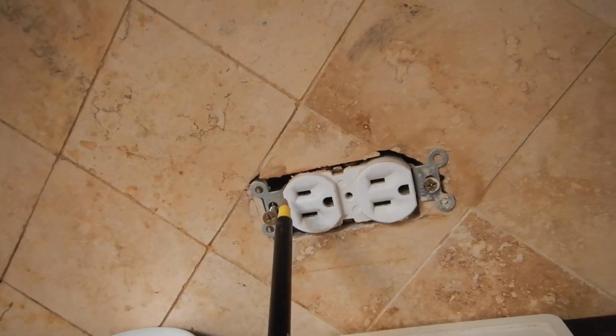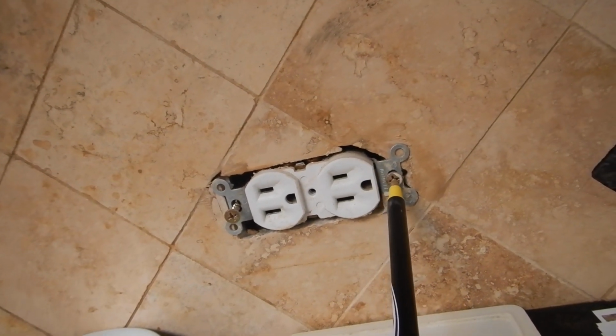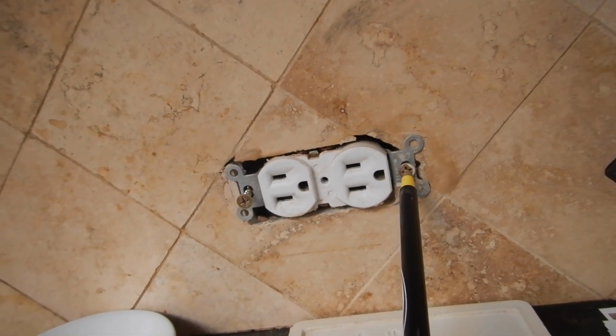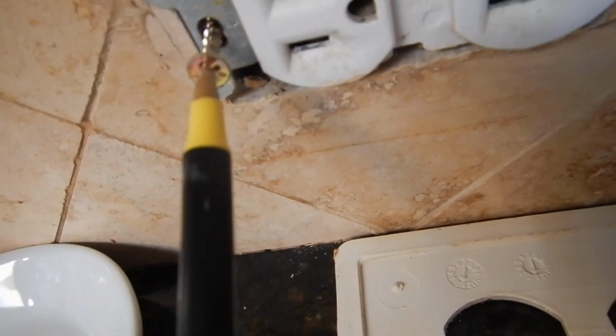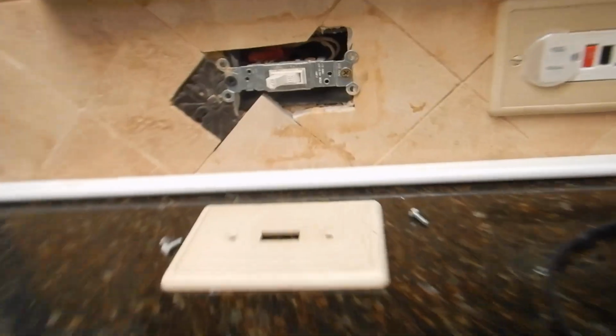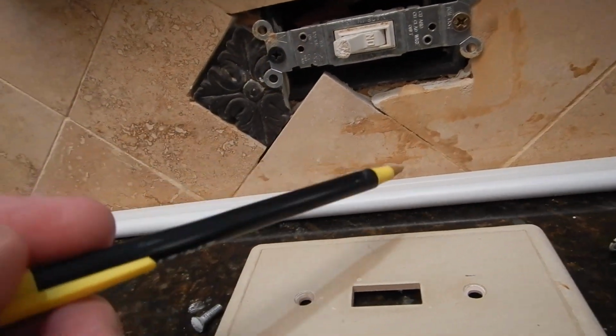But because the boxes are no longer positioned like they are, the screws would no longer work. They wouldn't reach because the screws weren't counting on this splashback. So they added these big old hairy screws, look at that. That screw right there will chew through some wires. It sure will. We got a drywall screw over here. It'll just chew right through some wires. Look at that. And so you should have some machine screws.